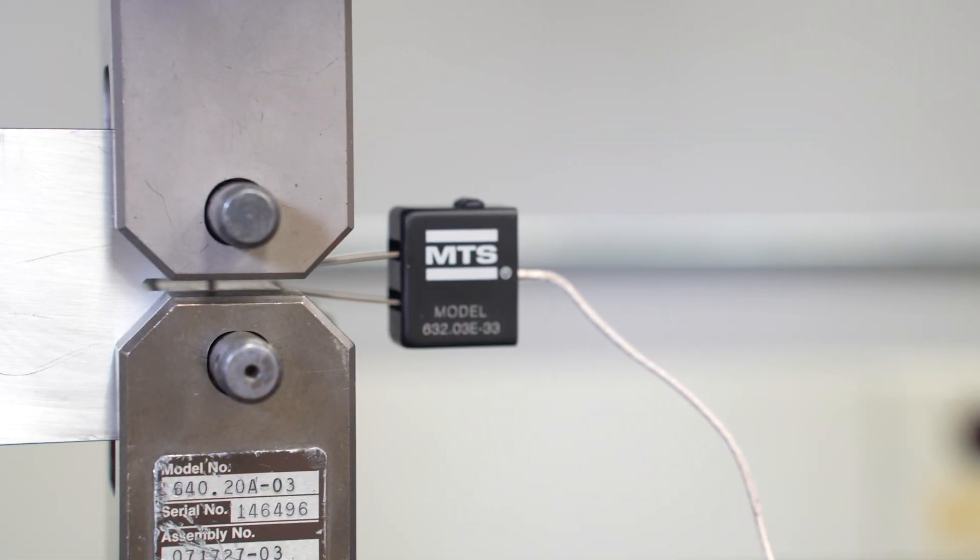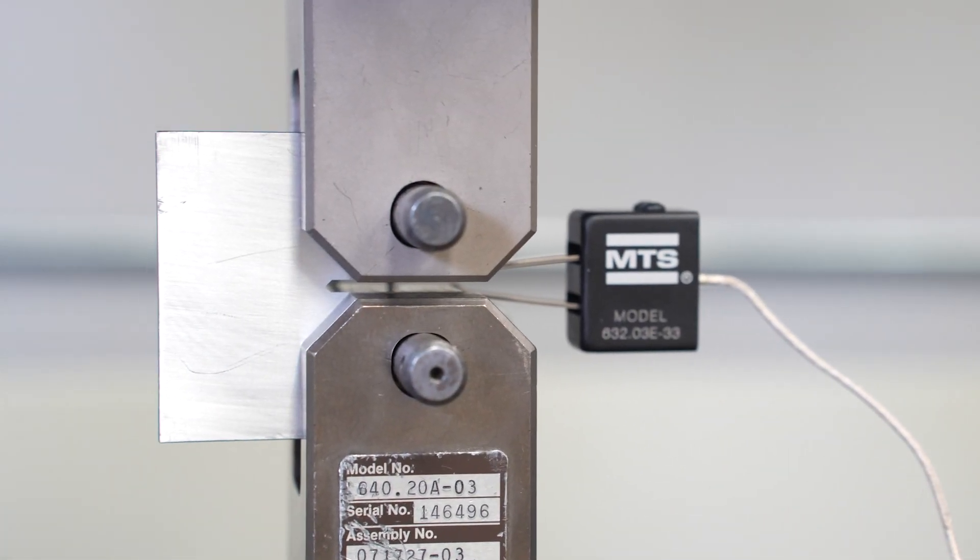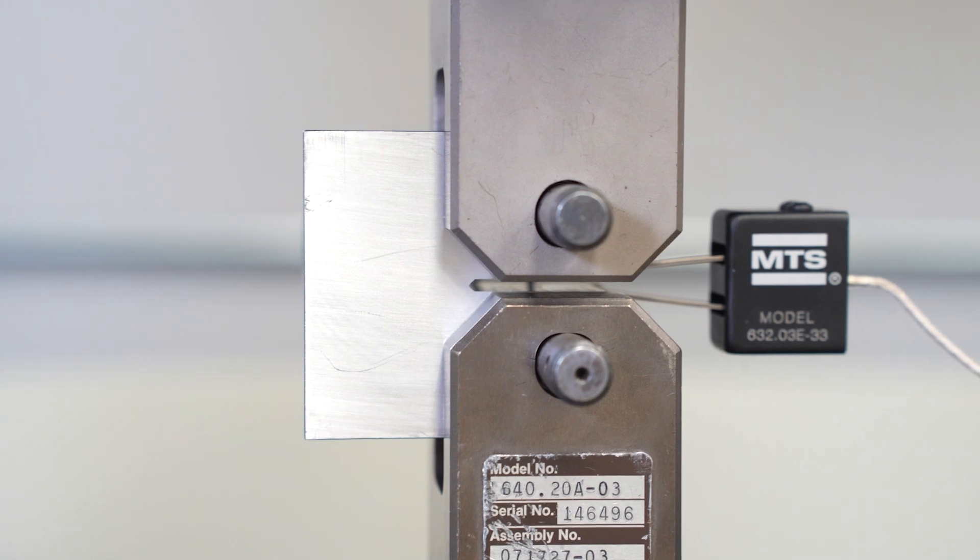Today we are running a K1C test in displacement control on aluminum 2024 T351. We are using a compliance crack length measurement technique to monitor the crack length during the pre-cracking and this pre-crack will end when the crack is approximately halfway through the specimen.